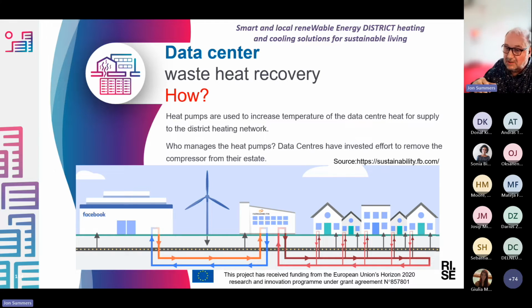In Sweden, where I'm located, the district heating networks run at very high temperature. In Luleå, for example, the winter temperature is over 110 degrees centigrade, and in summer around 72 degrees centigrade. That's quite challenging for data centers, where hot air is only between 25 and 35 degrees centigrade, and there are losses in trying to capture that heat into liquid form.